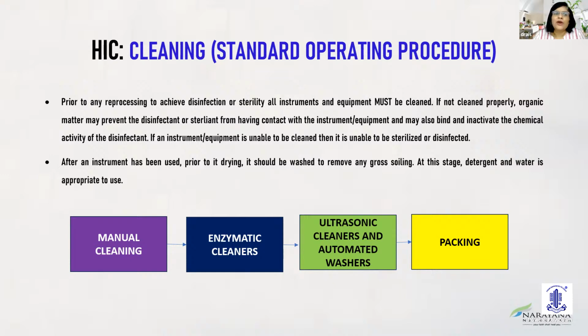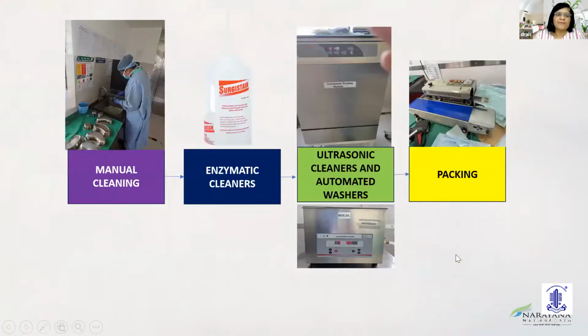If not cleaned properly, organic matter may prevent the disinfectant or sterilant from having contact with the instrument and may bind and inactivate the chemical activity of the disinfectant. If an equipment is unable to be cleaned, then it is unable to be sterilized or disinfected. So for manual cleaning, we then use enzymatic cleaners to clean the instrument. Then it goes to the ultrasonic cleaners and automatic washers, and eventually goes for packaging.